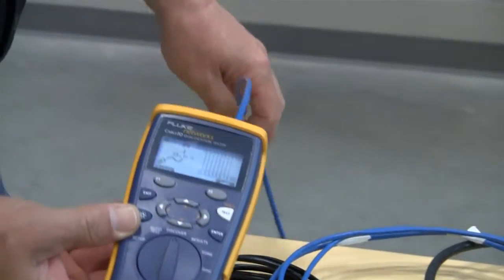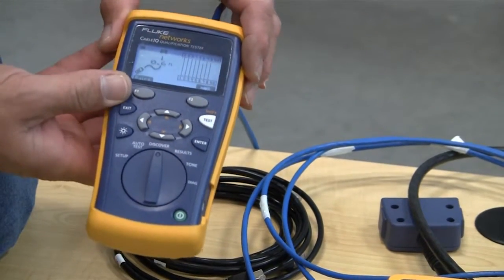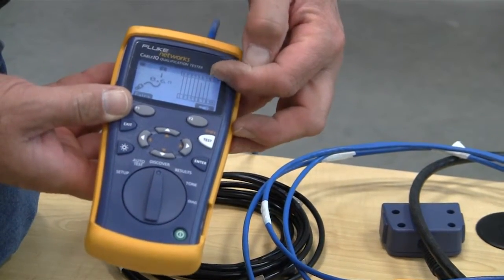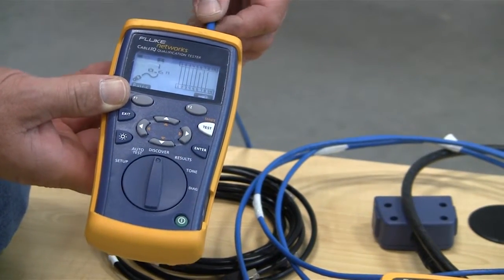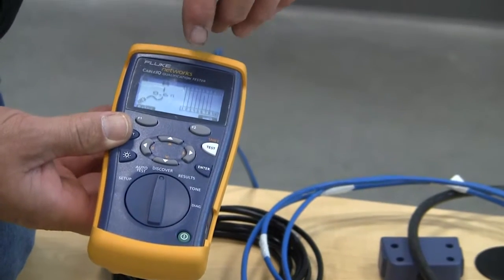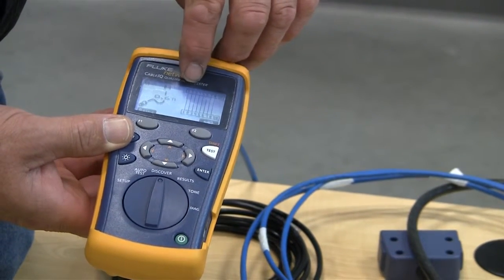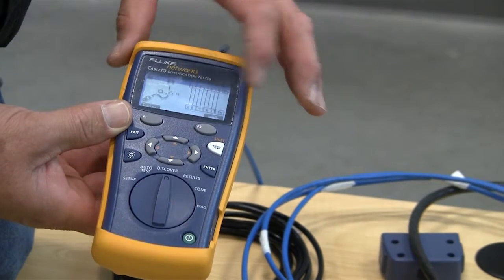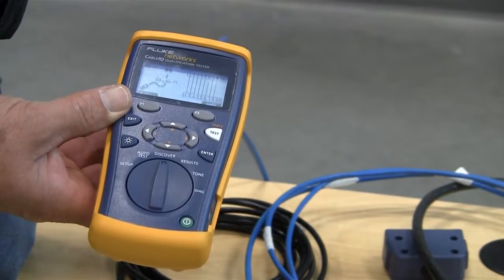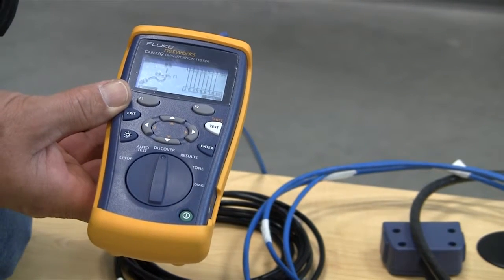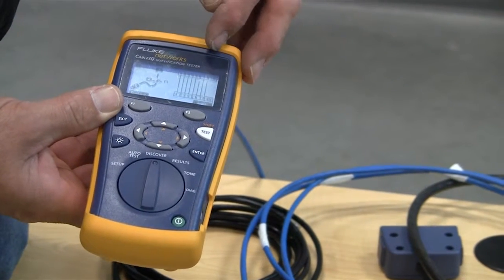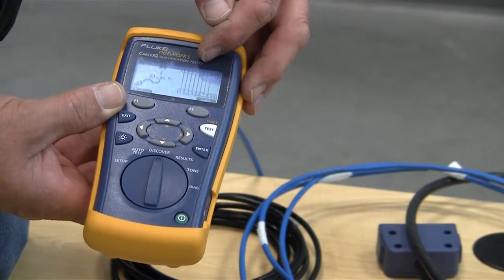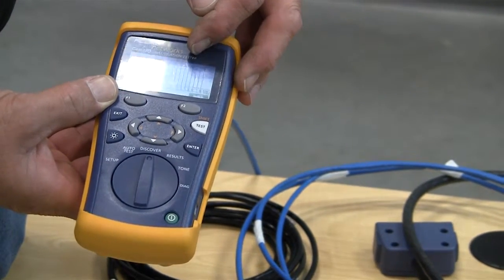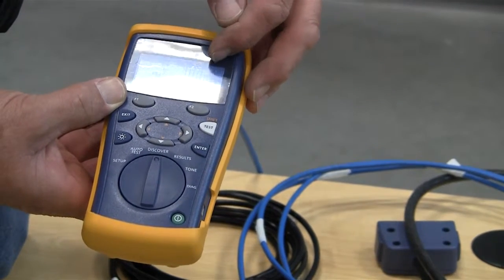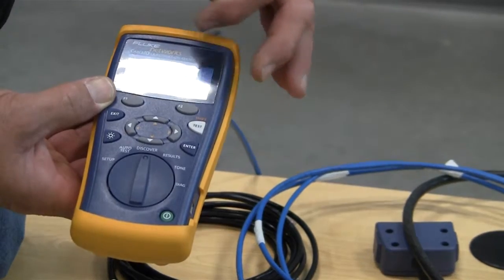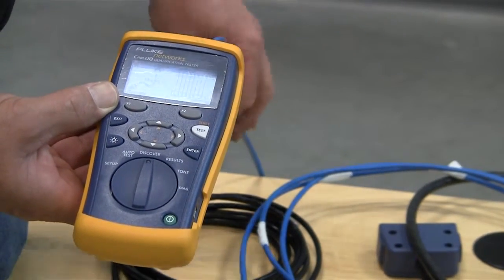One thing the qualifier will show is lines that don't go all the way to the top - those are the open wires in this cable. It gives you numbers across the top or bottom of the screen, corresponding to your 568A or 568B standard. You have to know which one you're using to know what color wire is the actual problem. In this case, wire 6, if this was 568B, would be your green wire, and wire 8 would be your brown wire, so we'd know which wires to look for when troubleshooting.